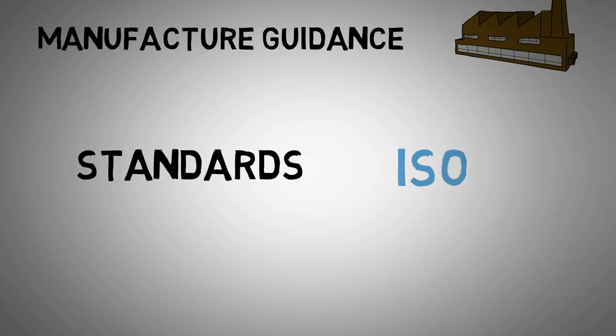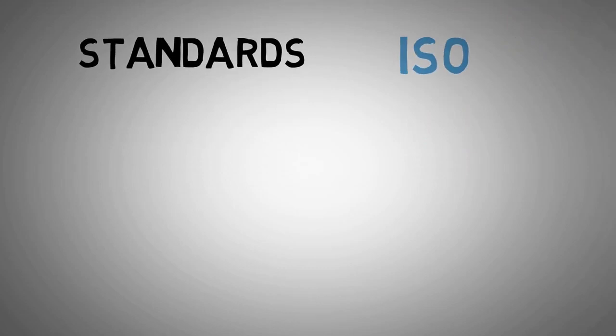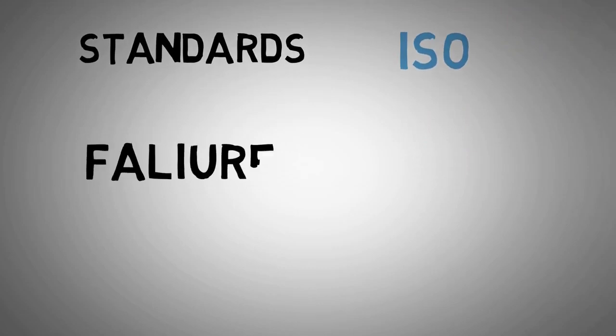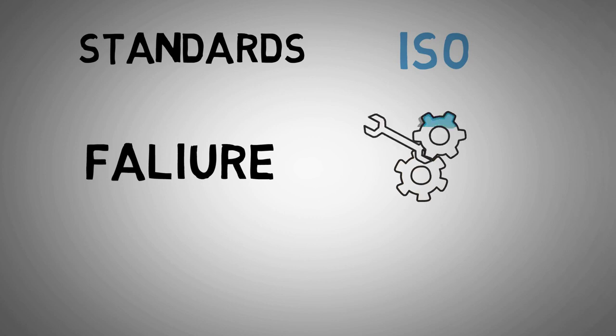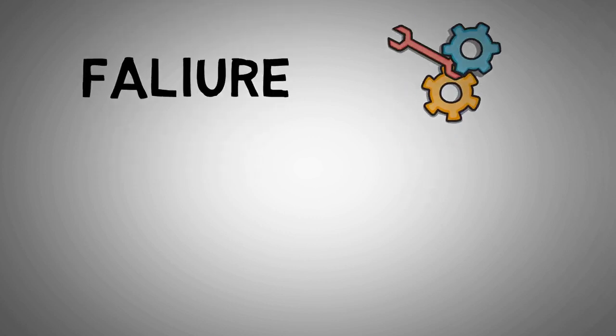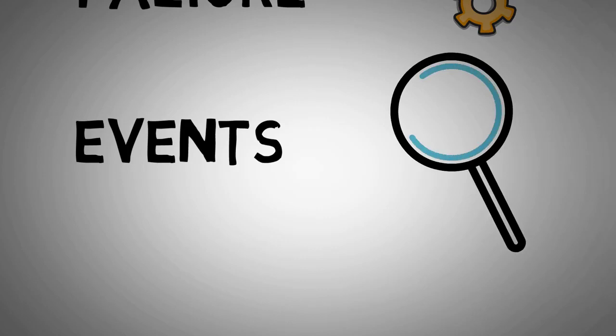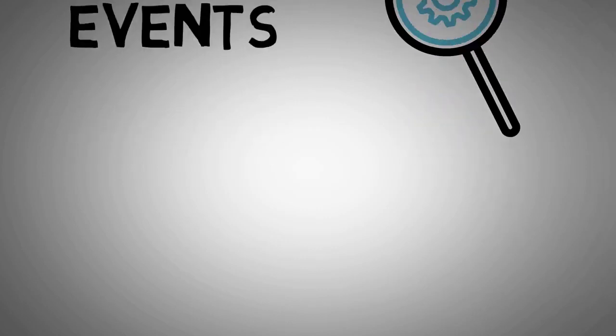and it will determine the frequency. Failure. Transmitters may need to be replaced and new equipment should be calibrated before being put into service. Events. Sometimes process operators may suspect equipment to be out of calibration due to abnormal readings. Investigatory calibration may be required to restore confidence in the equipment.